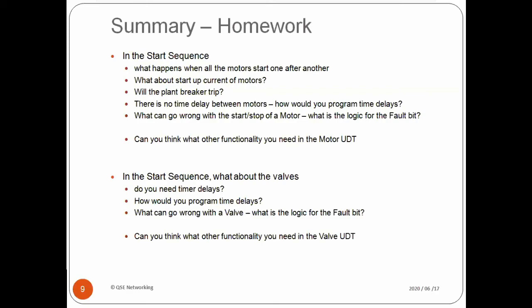You see we've now created a valve with 2 outputs and 2 inputs. So just to give you a hint, let's say the valve is closed, you know it's closed because we have a limit, and you put the open output on. First of all, it may not even move off the closed limit, and it may not even get to the open limit. So that's 2 faults.